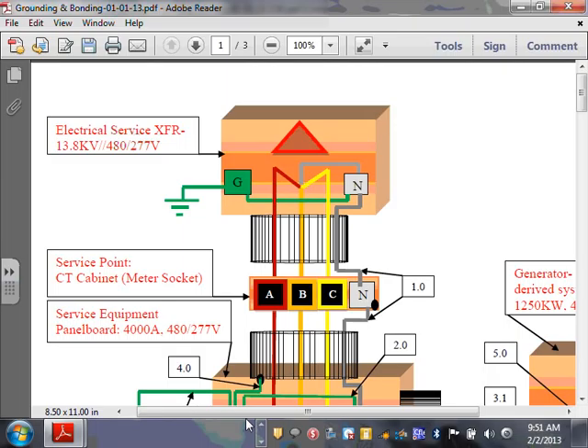Does that make sense? Do you guys do it differently? Anybody drive a ground rod right by the neutral and ground it right there at the termination box? It's very clear in the meter socket. Do you drive a ground rod at the meter socket and another ground rod at the panel? You're allowed to ground the neutral in the meter socket, but then you don't go into the panel and ground it again. Typically, you ground in one location, in the panel where the service disconnect means resides. Any comments, guys, about this?